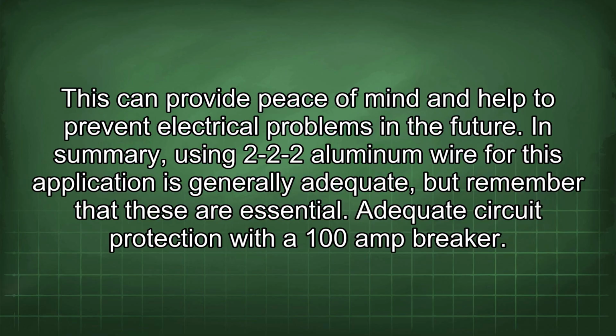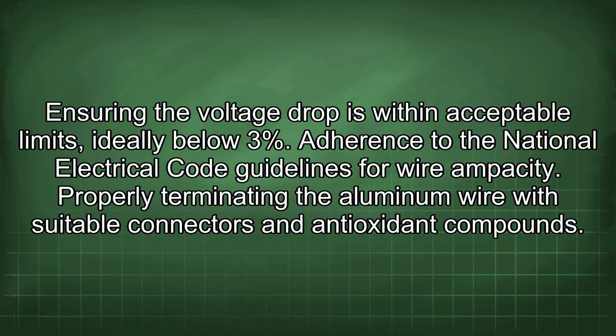In summary, using 2-2-2 aluminum wire for this application is generally adequate, but remember that these are essential: Adequate circuit protection with a 100 amp breaker. Ensuring the voltage drop is within acceptable limits, ideally below 3%. Adherence to the National Electrical Code guidelines for wire ampacity. Properly terminating the aluminum wire with suitable connectors and antioxidant compounds.